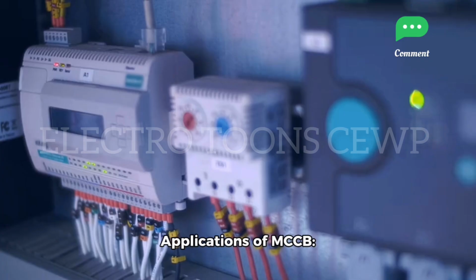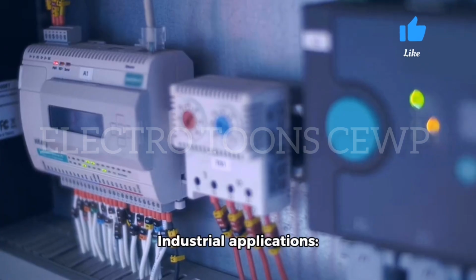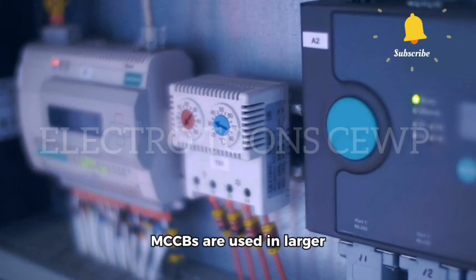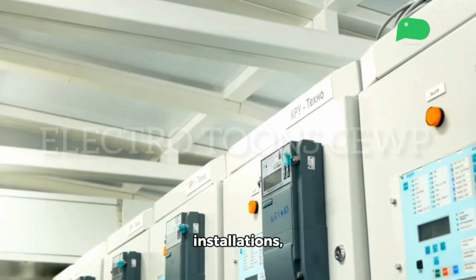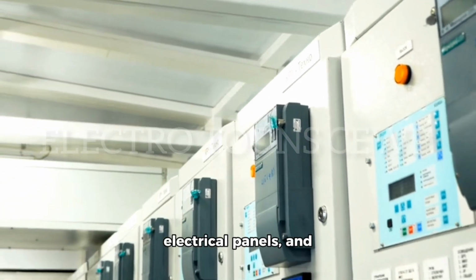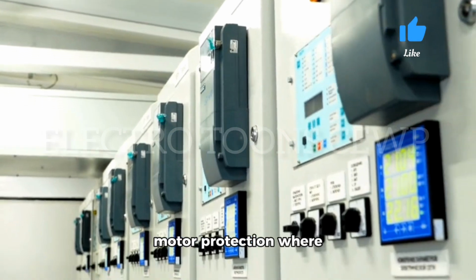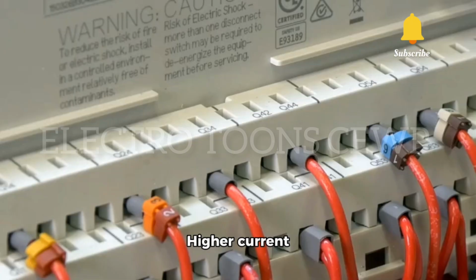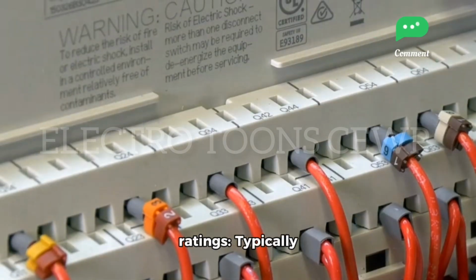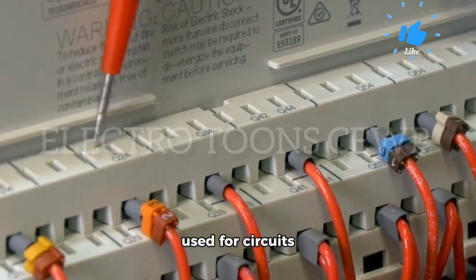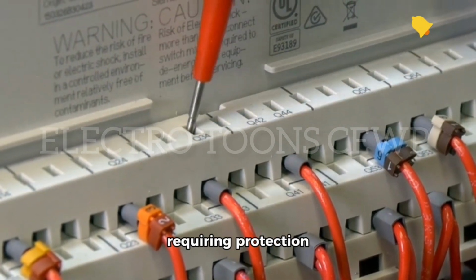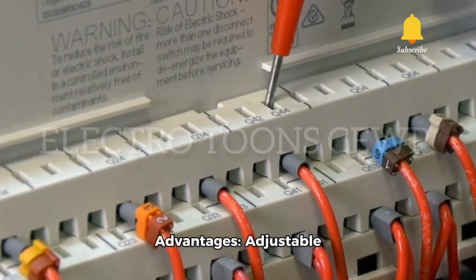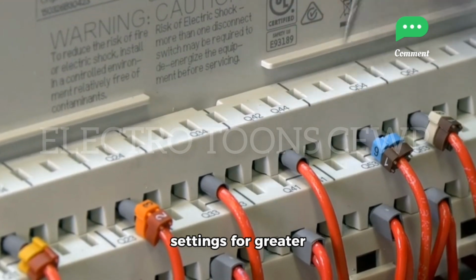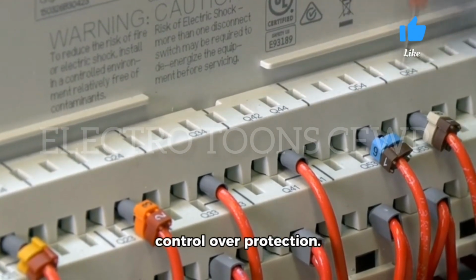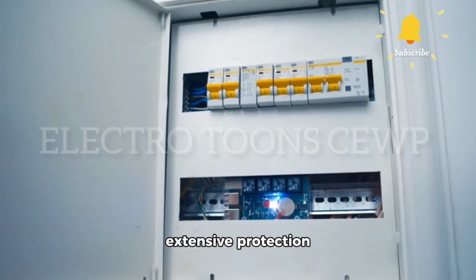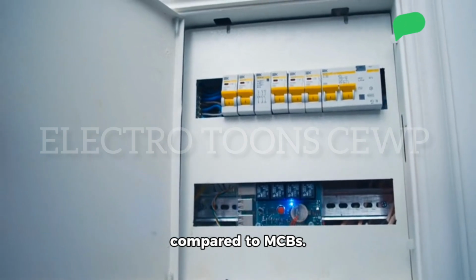circuit. Applications of MCCB. Industrial applications: MCCBs are used in larger industrial installations, electrical panels, and motor protection where high currents are common. Higher current ratings, typically used for circuits requiring protection of up to 2,500A. Advantages: adjustable settings for greater control over protection. Provides more extensive protection compared to MCBs.